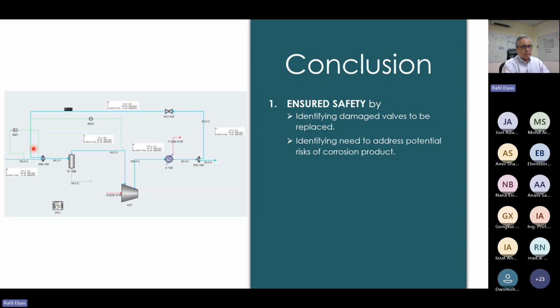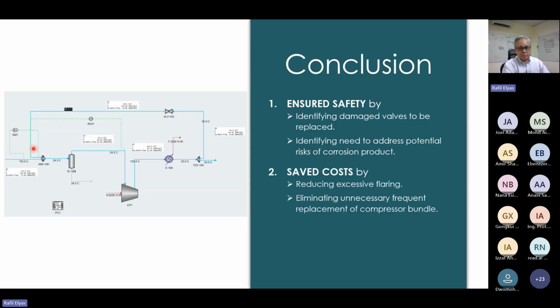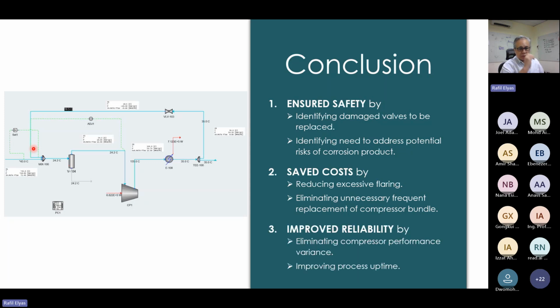So we essentially identified the damaged valves to be replaced, sent that out, and wrote a report again about the corrosion. Initially the CO2 levels were supposed to have been lower for the system, so the material that was selected, carbon steel, did not have the resiliency to deal with corrosion. The other solution, unfortunately, albeit a very expensive one, was to change out certain sections to prevent corrosion. So this is one of our operations troubleshooting cases.